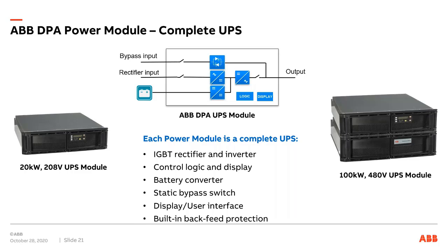And ABB developed 2 power modules, slide-in power modules for modular UPS. This is not from 14 years ago, this is the latest generation of that, but based on that concept that the power module is not just a rectifier and an inverter, it's a complete UPS. So today in the North American market, we have 2 different lines of product, a 208 and a 480 volt. The 208 is based on the 20 kW, the 480 on 100 kW, and in the center of the slide here, both of them are complete UPSs. They're both based on the latest generation IGBT for the rectifier and the inverter. They have full microprocessor control logic, static bypass, and built-in backfeed protection, which by the way is a UL requirement. It's all in the box, but the box is a module that slides in.